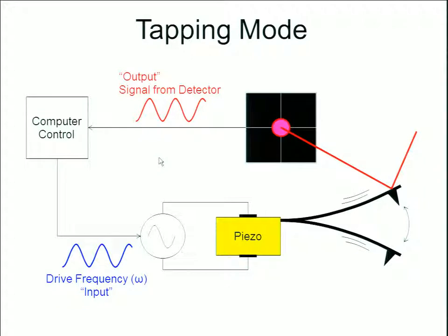What we look for is the difference between our drive frequency and what we actually see occurring on the cantilever — measured from the phase shift or amplitude change of the output signal. This phase shift or amplitude change occurs because the tip is now interacting with the sample and is no longer in free space.